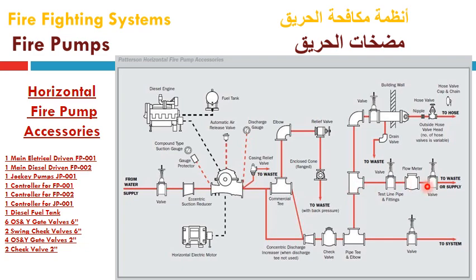And then we can also use the flow meter line with two isolation valves. It's recommended to be OS&Y gate valves, to the waste or again to the supply tank as mentioned here. And we can also use this test manifold for hose valves, which can be connected to the drain valve as mentioned before, to the waste with a ball valve for washing the line, and also we will connect with a flanged hose valve, or with a nipple if it is threaded type, to connect the hose valve with the hose valve header.